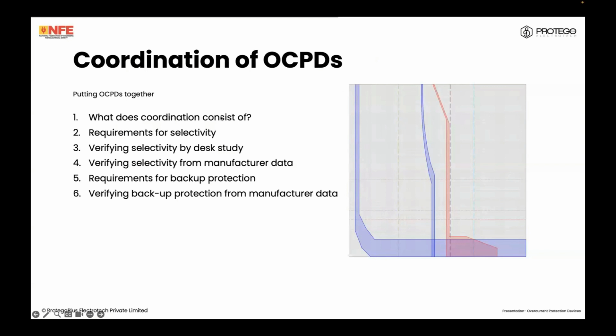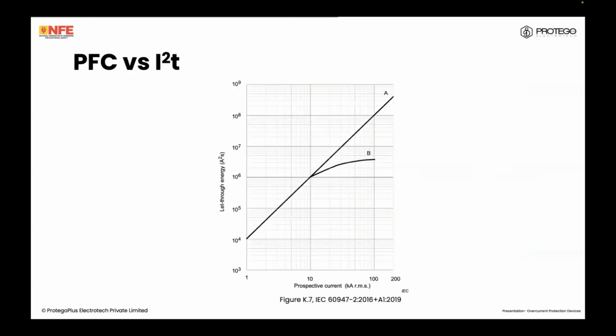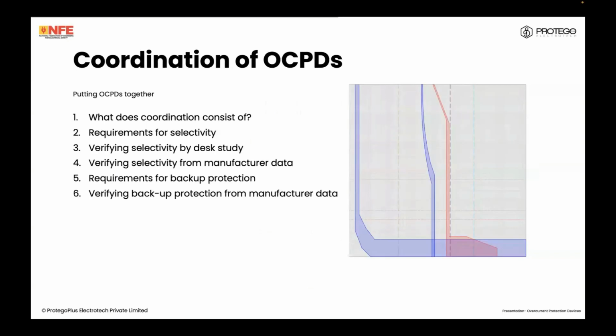As we said, this is selectivity plus backup protection, or what was earlier known as discrimination plus cascading. We look at requirements of selectivity. How do we achieve these things? We look at figuring out how to verify if there is selectivity present between two overcurrent protection devices by something called desk study, which is a comparison of these characteristics. We look at verifying selectivity from manufacturer data, and we look at requirements of backup protection.